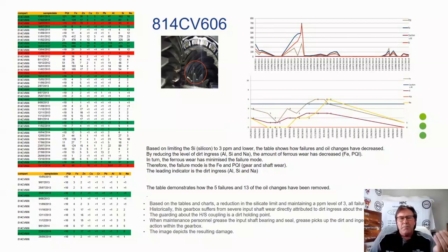Some of the biggest impacts there were actually killing this gearbox with kindness by lubricating that input shaft seal, to prevent contaminant from getting in. We were starting to present with thermal expansion and contraction, and it was drawing the contamination in.